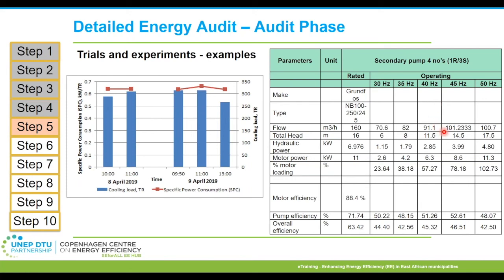If you operate at 50 hertz, power consumption is slightly higher; at a lower frequency, power consumption comes down. But another challenge is that at very low frequencies, the head developed would be minimal, so it wouldn't effectively push water to the source or user end.